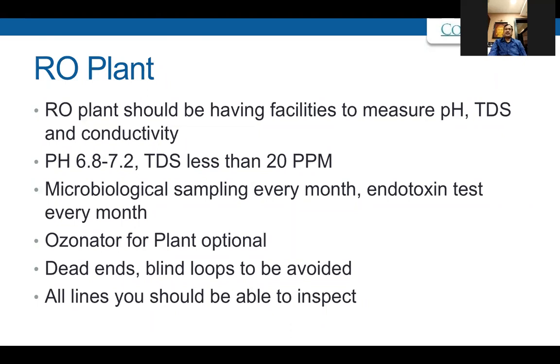Many of the RO water plants are coming with online pH as well as online TDS, which comes as a display. TDS, if it is less than 20 ppm, it is good. The pH should be around the range of 6.8 to 7.2. Microbiological testing is very, very important for the RO plant as well as for dialysis. Endotoxin, as per European Union standards, and as far as Indian standards are also concerned, every month we need to do the endotoxin test. Ozonator is an optional requirement. If it is there, it is good for the plant. Even if it is not there, it is not compulsory under NABH also. There should not be any dead ends or blind loops. All lines should be regularly inspected and cleaned appropriately.